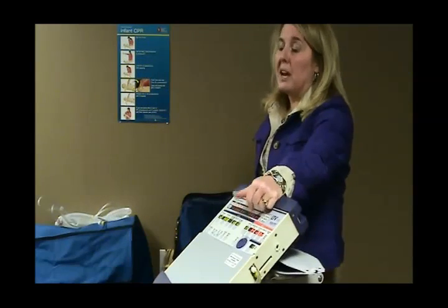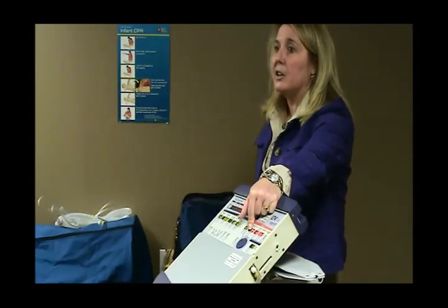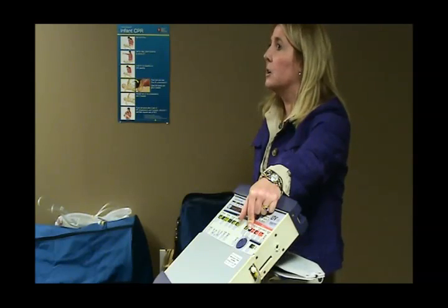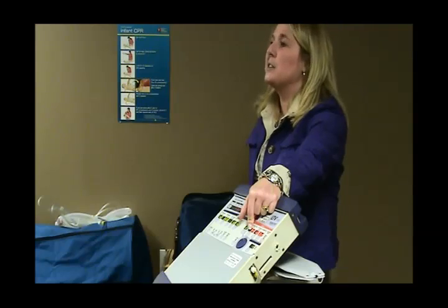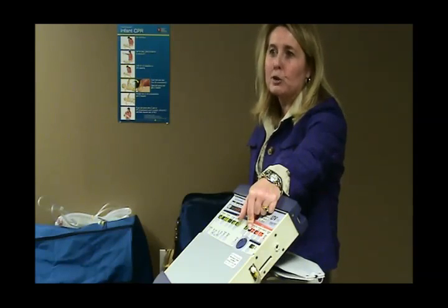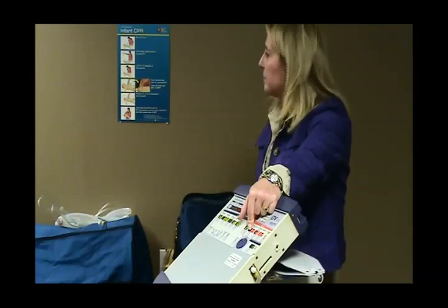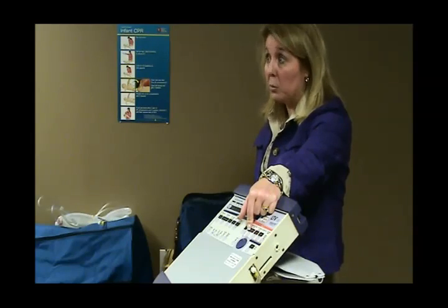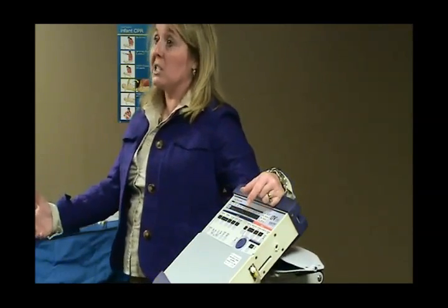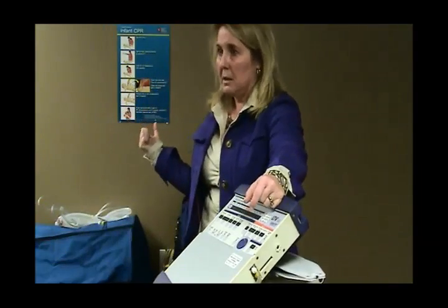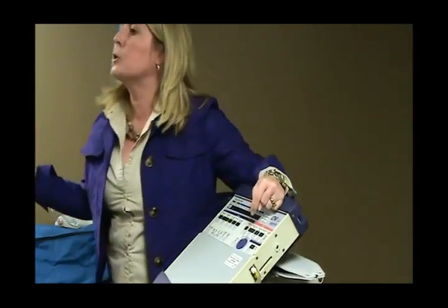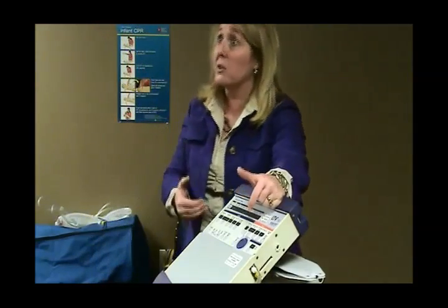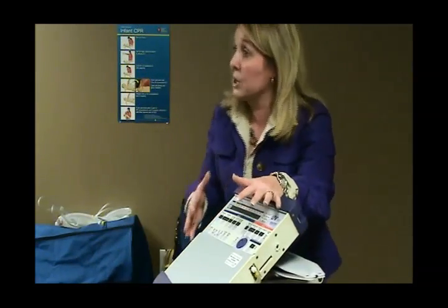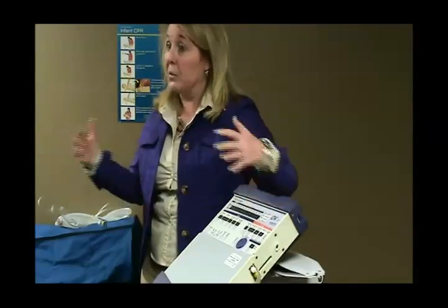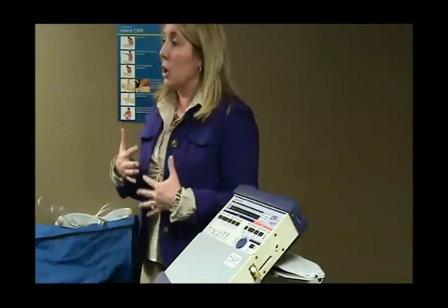If you go into a home and you see somebody's run that sky high, and you go, whoa, whoa, whoa, why is that at 80? And they say, oh, well, every time I give him a bath, it high pressures, we just want to get rid of those alarms, so we ran that up. No, no, no, that is your pop-off, which means that's the point at which it releases pressure from the ventilator circuit to ambient, okay? It will go up to 100 centimeters of water pressure. We have to do that because our ventilator is used in critical care as well. A version of our ventilator is used by the military to ventilate big guys with chest traumas. So we have to be able to deliver big pressures and not alarm for that.